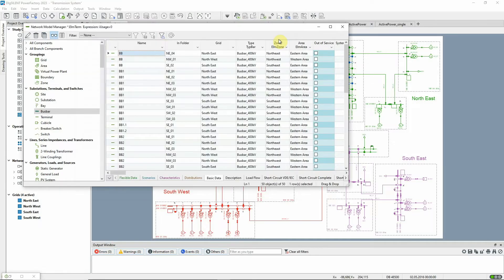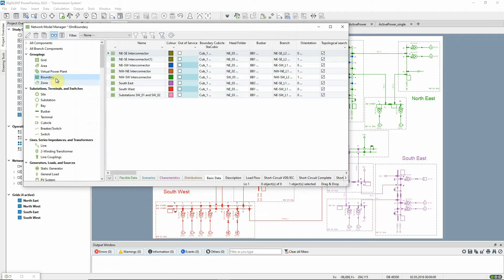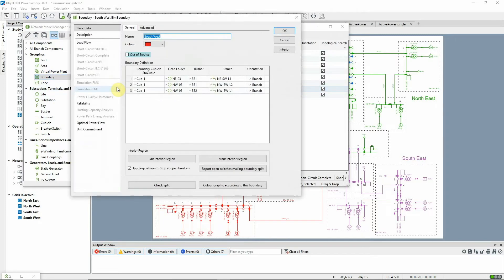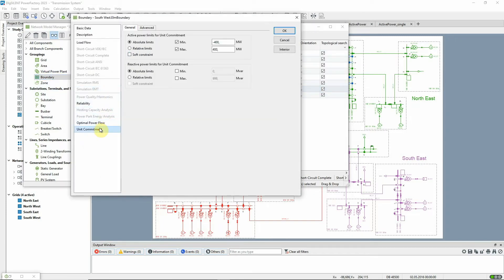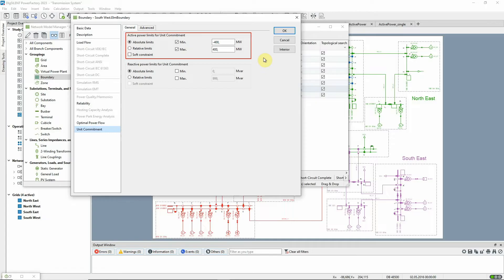Also, for the southwestern part of the network, a boundary constraint is defined and observed. The boundary flow constraint limits the active power flow to between plus and minus 400 megawatts.